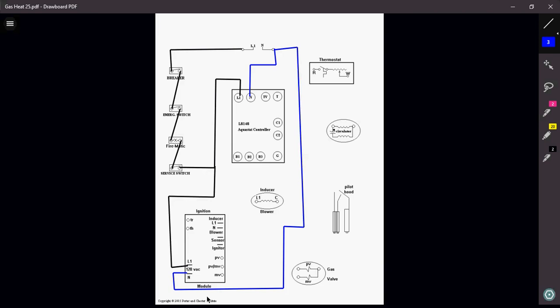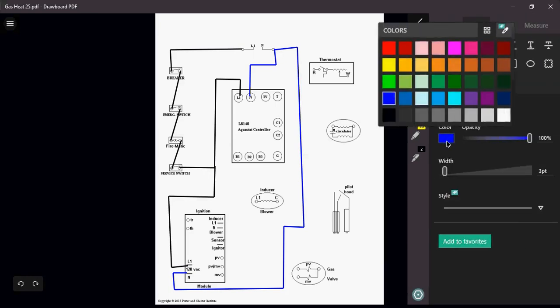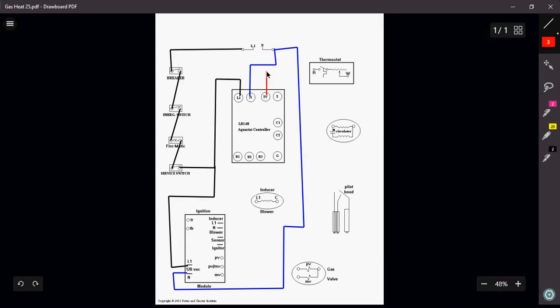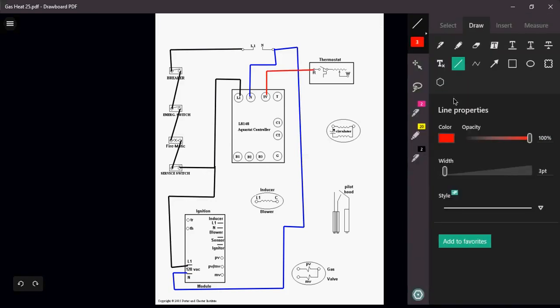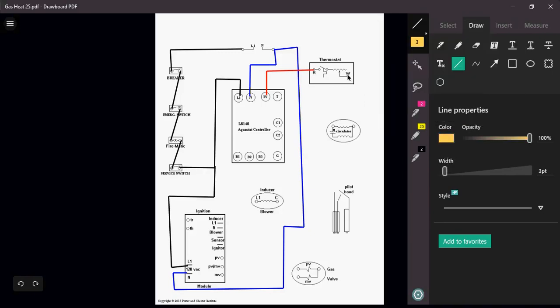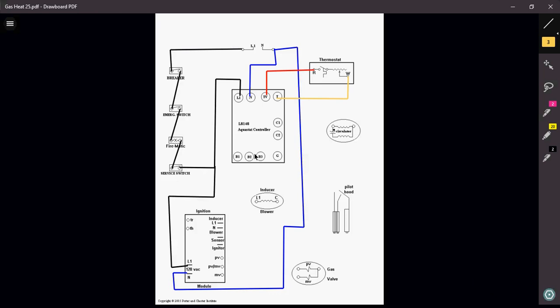Out of my Aquastat I got to power up my thermostat. Remember the thermostat is getting power from the transformer inside the Aquastat. So I'm going to come out of my TV here into my R. Out of my W, I'm going to come right back to my T. That will complete the circuit so once the thermostat calls for heat, I have now completed the circuit inside the Aquastat, which will then send the signal out to the rest of my components so that I can start the heating process.